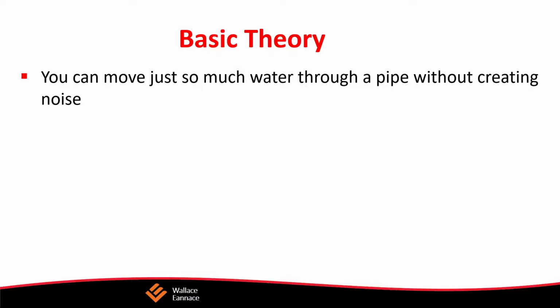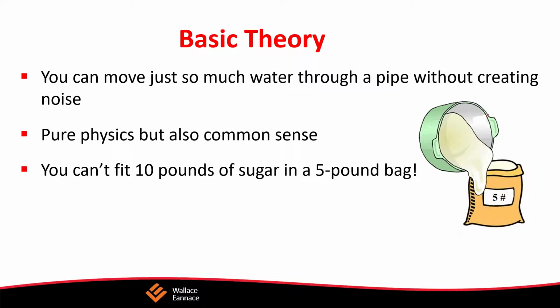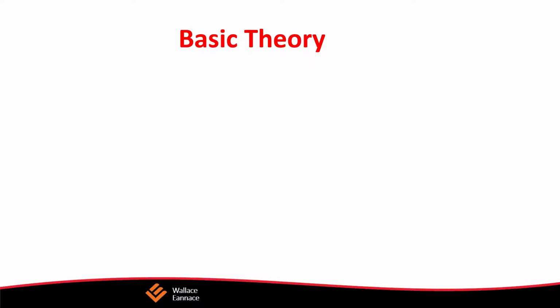You can move only so much water through a pipe without creating noise. Now that's common sense, but it's also physics. As you know, you can't fit 10 pounds of sugar in a 5-pound bag. If you try to put too much flow through a pipe, the circulator will certainly try to put it through, but you can only move so much water through a certain diameter pipe.